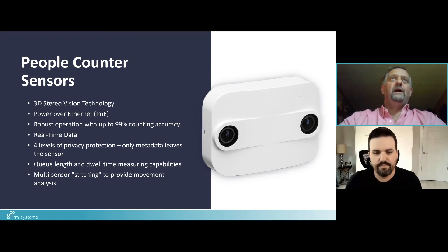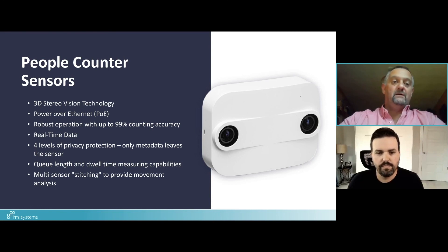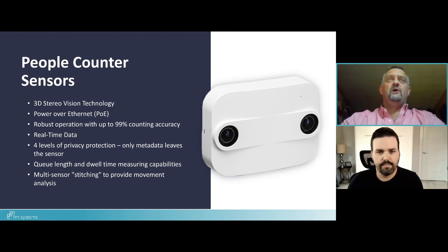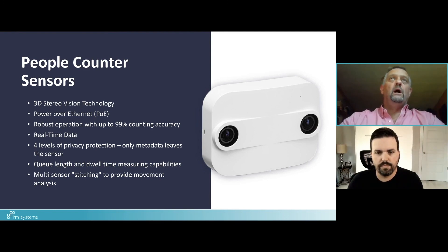For a small phone booth designed for single occupancy, an area sensor isn't needed — a PIR sensor works fine. For collaboration and soft seating spaces, PIRs don't work; area sensors are ideal. And then there are spaces where you simply want to know how many people are in the space, not necessarily what they're doing — that's where people counter sensors come in.